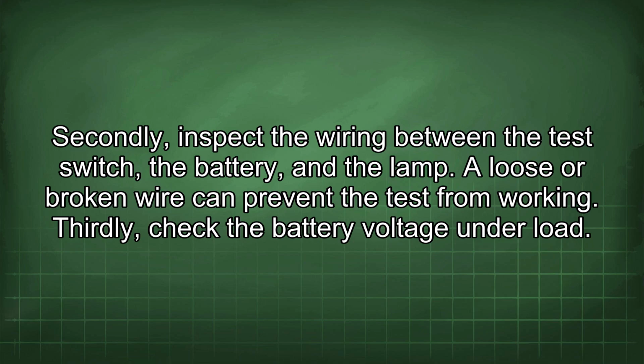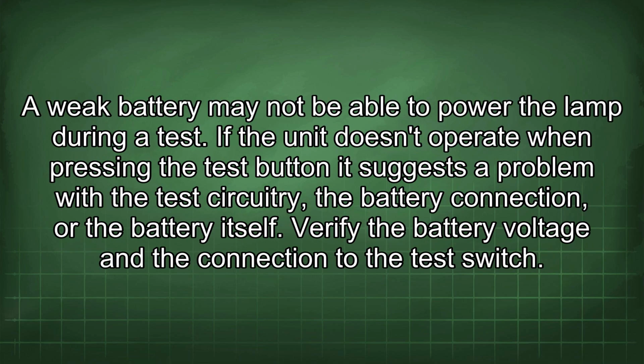Thirdly, check the battery voltage under load. A weak battery may not be able to power the lamp during a test. If the unit doesn't operate when pressing the test button, it suggests a problem with the test circuitry, the battery connection, or the battery itself. Verify the battery voltage and the connection to the test switch.